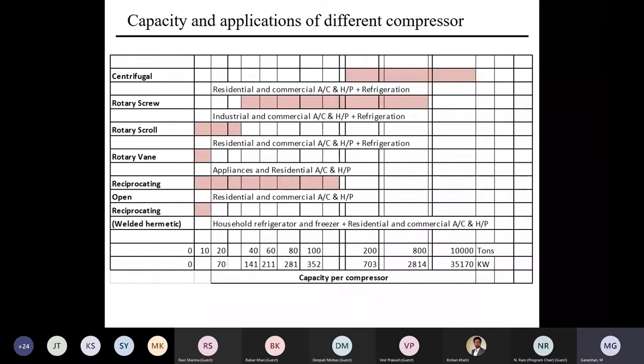If you see the capacity and application of the different types of compressors, centrifugal starts with the higher range, basically from a minimum of 200 to 10,000 tons. Rotary, from 40 tons, can go as high as 800 ton chillers. Rotary scroll is a very small range, up to only 30 to 40 tons. Rotary vane is very small, 10 tons. Reciprocating, as you all know, is from 10 tons and can go as high as 150 tons. So this is how it is classified. Welded hermetic and semi-hermetic can go up to 300.